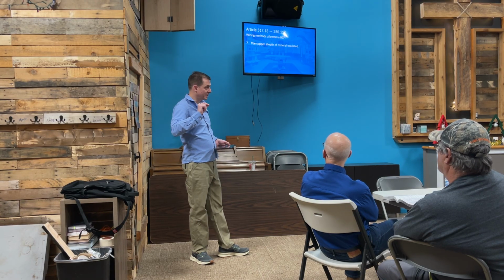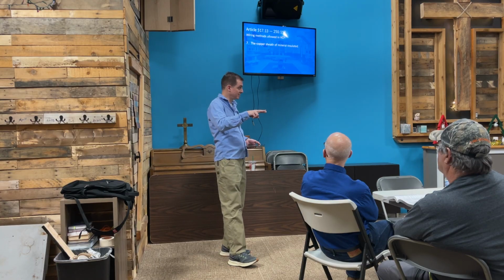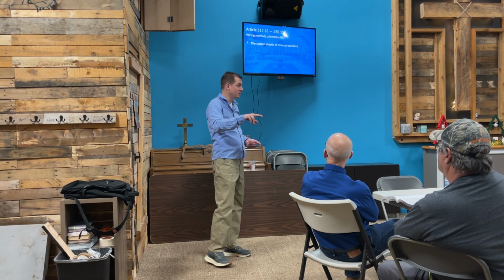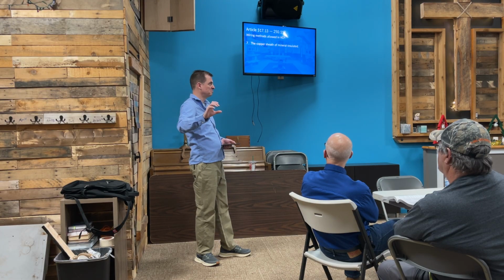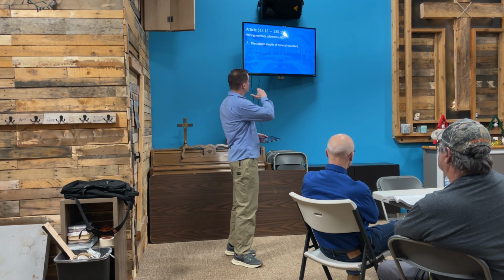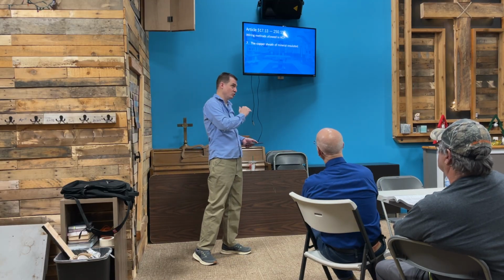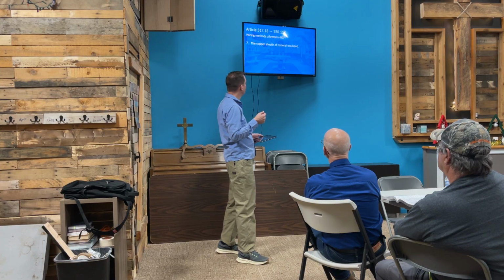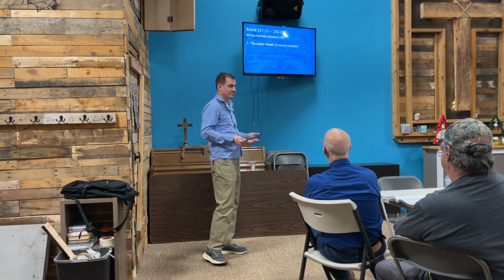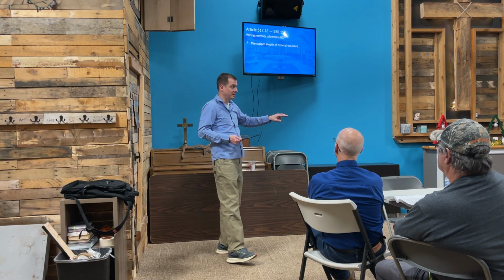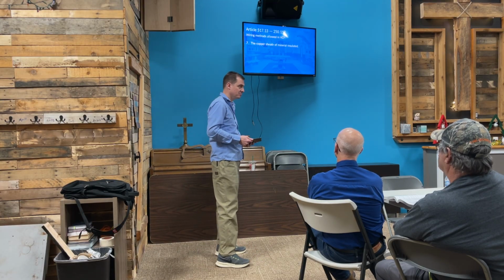I get it's really not a cable - it's like the soft copper you see for plumbing, but inside that soft copper are at least 2 conductors, supply and return, hot and neutral, and the whole thing is encased in a chalk-type material. It's hard, like some type of compound, and you're probably going to see it in a place that's got heat - autoclaves, things that make a lot of heat. So we use this mineral insulated tubing, I think is probably what it's called. I think I chopped some of that off. But you can use that - again the best way to describe it is like soft copper with conductors inside, filled with some type of heat insulating material.